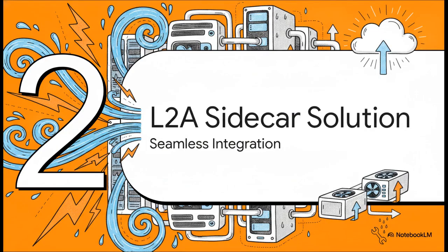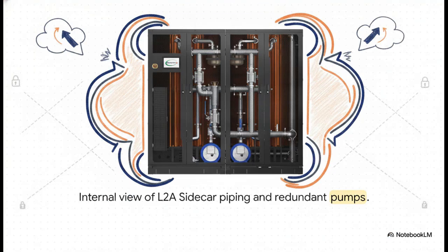Which brings us to Section 2, the L2A Sidecar solution. So how exactly do you get liquid cooling performance without installing all that liquid facility infrastructure? When you look inside the L2A Sidecar, you immediately notice this intricate, heavy-duty piping and those blue N+1 redundant pumps down at the base. What you're looking at is a fully closed-loop design - the liquid cooling loop is 100% contained within the rack, totally isolated from the facility's primary water system.